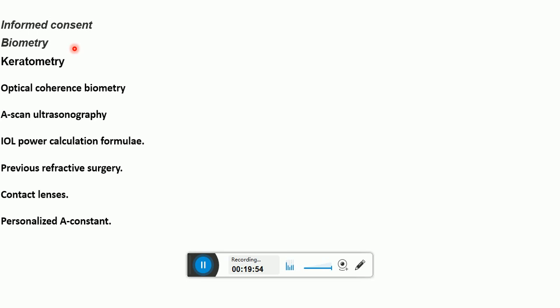This is commonly carried out with the interferometry apparatus used to determine axial length. But if this is unavailable or unsuitable, manual keratometry, for example, Javal-Schiötz keratometer, or corneal topography can be performed. And there is OCT, optical coherence biometry, not OCT. It is a non-contact method of axial length measurement that utilizes two coaxial, partially coherent, low-energy laser beams to produce an interference pattern, partial coherence interferometry.